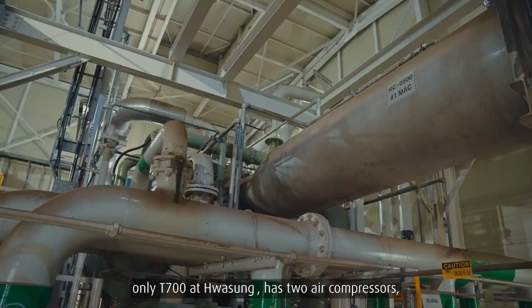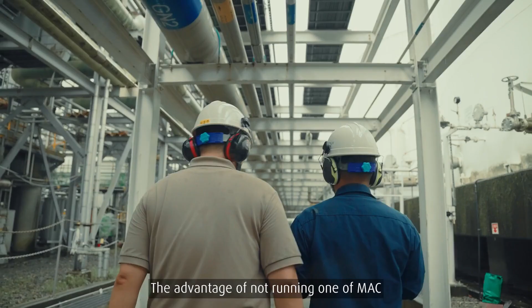Among the plants in the Hwaseong and Yongin sites, only T700 at Hwaseong can have 2 air compressors, so if the customer demand decreases, we can turn off one of the air compressors to operate the plant at 50% plant load. The advantage of not running one of the MACs while maintaining the same amount of product supply is savings. A simple idea has reduced the big power consumption, and this project helped to maintain the purity of the column during the summer. It is a good example of improving operational stability and productivity.